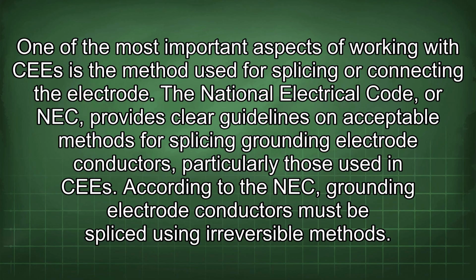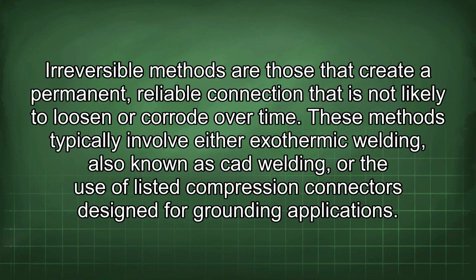The National Electrical Code, or NEC, provides clear guidelines on acceptable methods for splicing grounding electrode conductors, particularly those used in CEE. According to the NEC, grounding electrode conductors must be spliced using irreversible methods. Irreversible methods are those that create a permanent, reliable connection that is not likely to loosen or corrode over time.